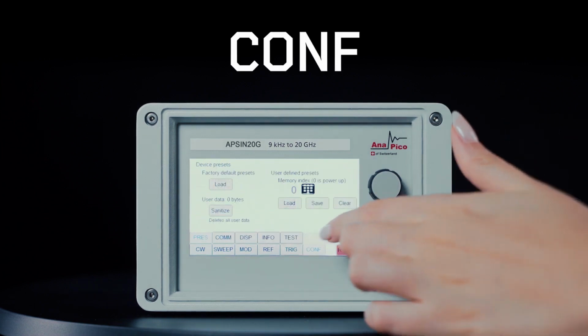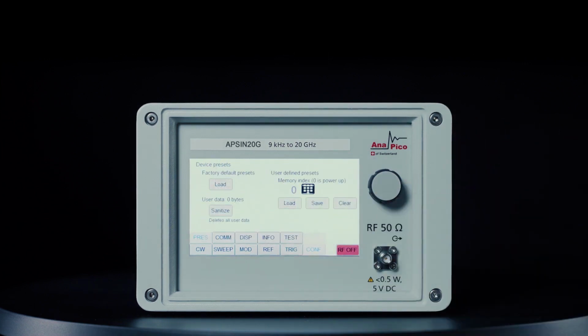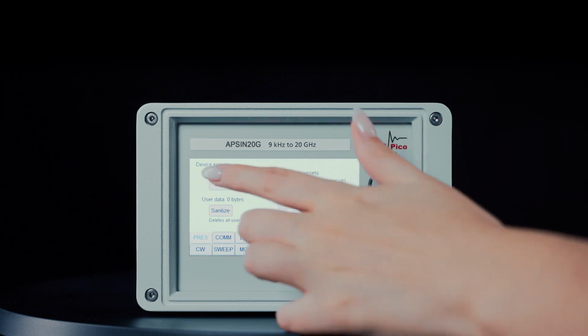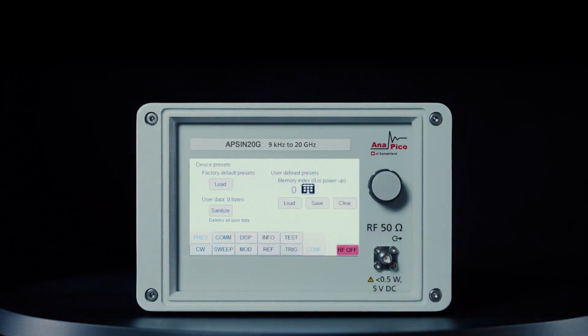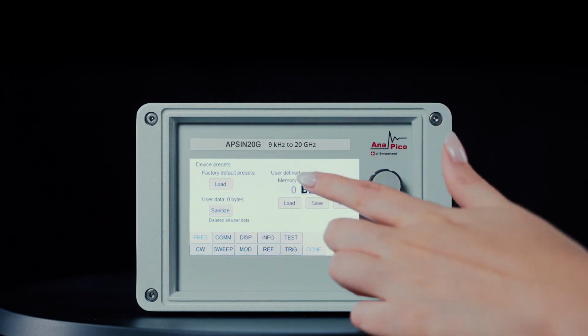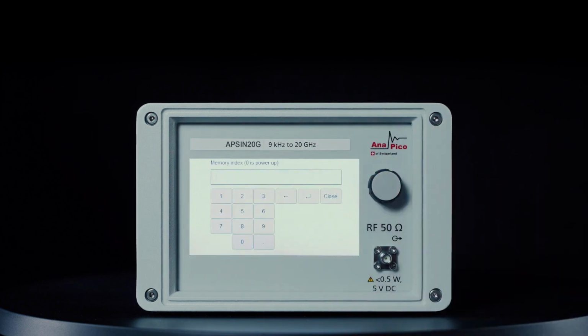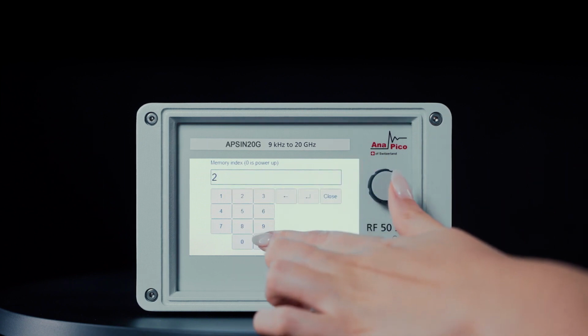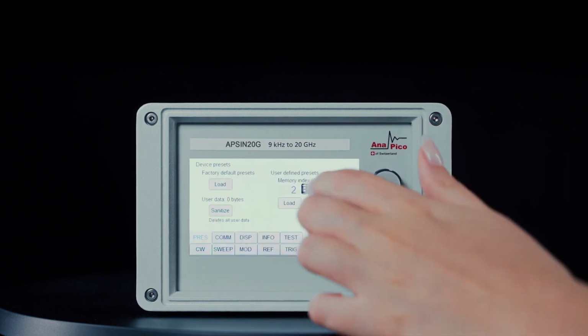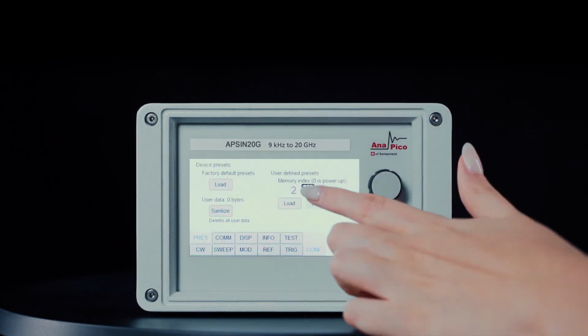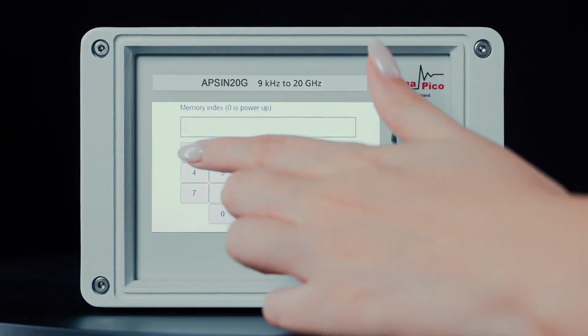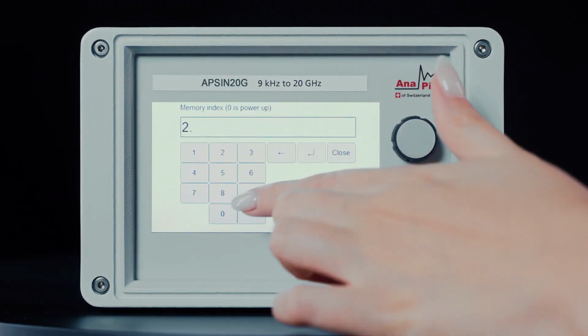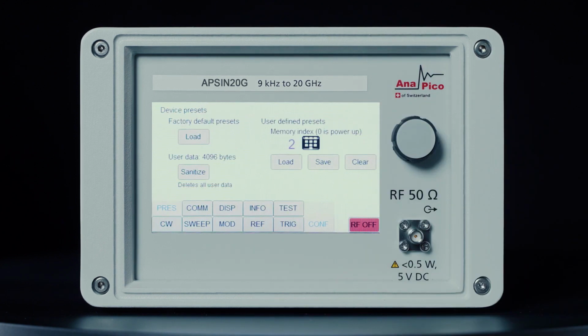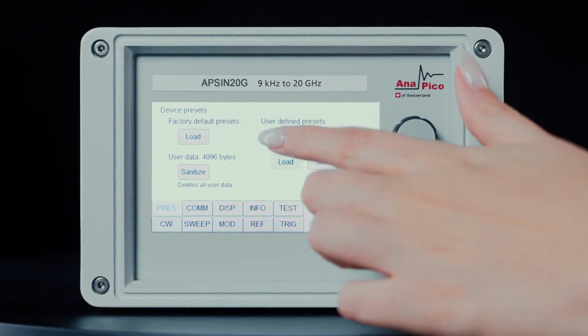Conf button. The configuration button is responsible for the instrument settings. If the load button is pressed, the factory settings of the generator will be set. The user can set their own instrument settings under a certain index. Save each type of setting under its own index. To load a setting from the user settings, select an index in the instrument memory and press the load button.